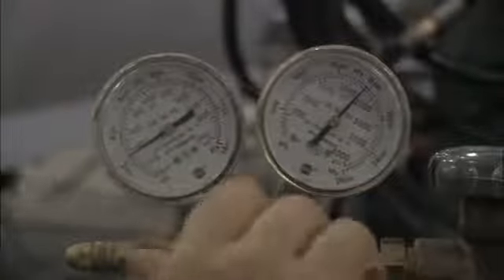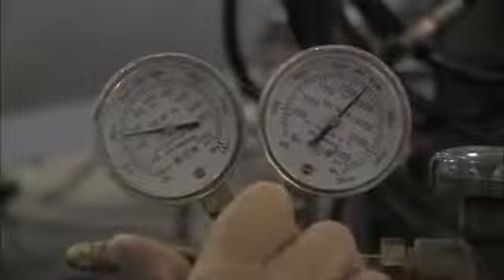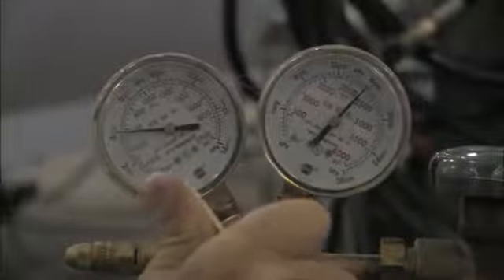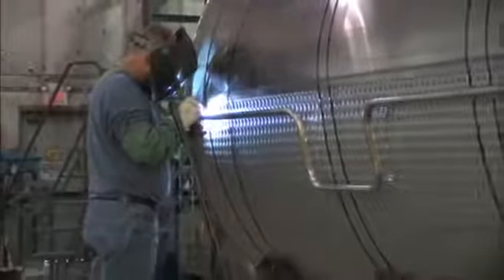We pressurize the evaporators with dry nitrogen gas at 560 psi to create an 80,000th of an inch space between the inner and outer surfaces for the refrigerant. We maintain that pressure for 15 minutes and measure any pressure losses indicative of leaks. The inflated panels are then filled with refrigerant oil containing a fluorescent dye to test for minute leaks using an ultraviolet lamp. Stainless steel refrigeration lines are then installed and the entire system is tested again for leaks using the UV lamp.